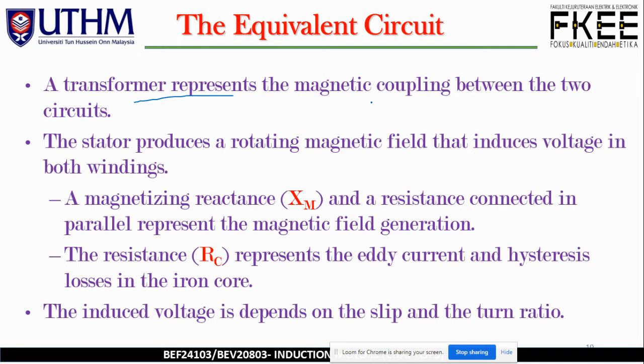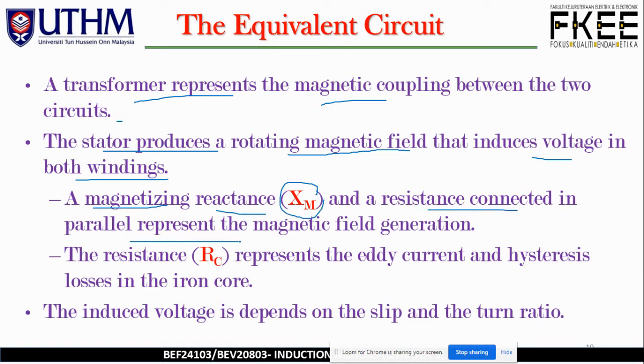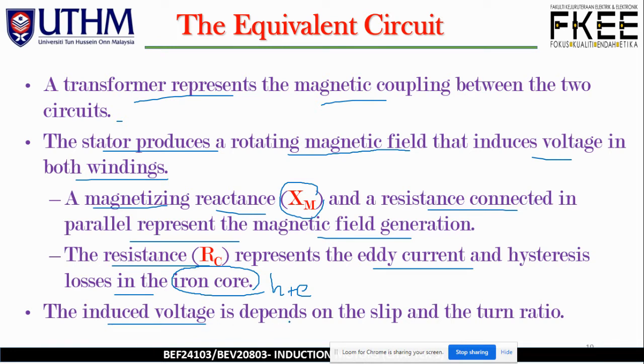A transformer represents the magnetic coupling between two circuits. The stator produces a rotating magnetic field that induces voltage in both the stator and rotor windings. The magnetizing reactance XM and a resistance RC connected in parallel represent the magnetic field generation. The resistance RC represents the eddy current and hysteresis losses in the iron core, known as core losses. The induced rotor voltage depends on the slip S and the turns ratio.